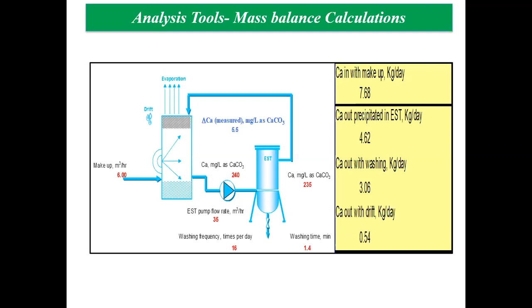So instead of depositing that much calcium in the system or keeping it in suspended form, this equipment is actually taking that calcium out of the system. By that, it is protecting your condenser loop from scaling, right? You're not allowing the calcium to sediment somewhere else. First of all, you are allowing it to sediment or precipitate inside the tank. Then you are eliminating that, instead of keeping it in suspended form or allowing it to form scaling in your system.